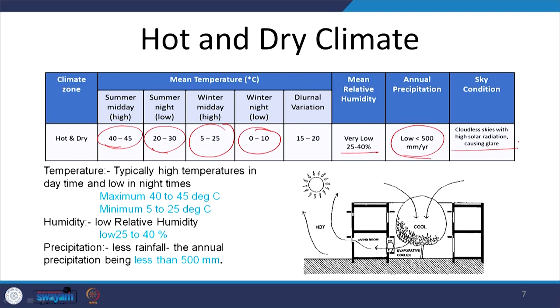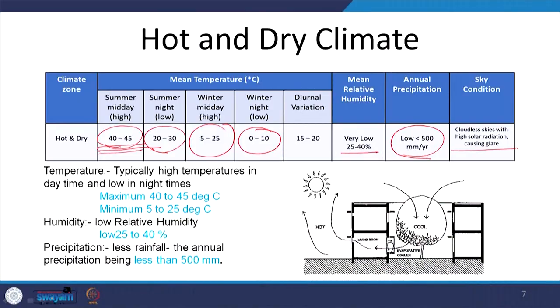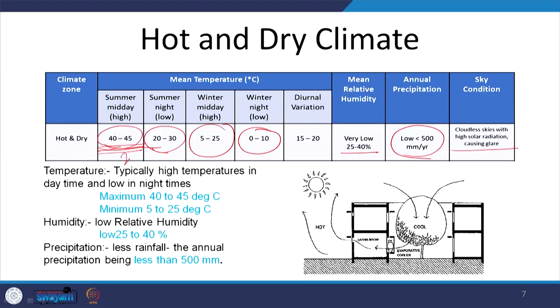For the given environmental conditions of hot dry climate, certain physiological objectives can be clearly identified. With summer temperatures at 40–45°C, the physiological objective of design is to bring down the ambient dry bulb temperature to approximately 25–30°C — a reduction of about 20°C. In winters on the other hand, we may need to increase the temperature by around 15°C. Both aims can be achieved by reducing heat transfer during extreme weather conditions.